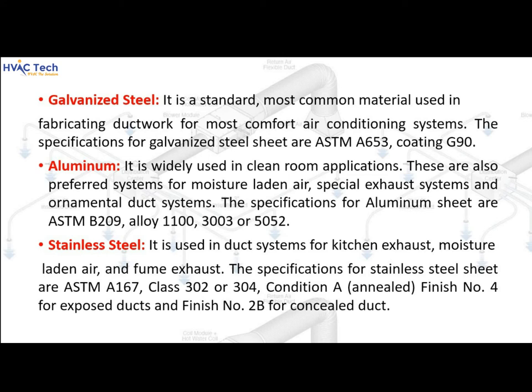Stainless steel is used in duct systems for kitchen exhaust, moisture-laden air, and fume exhaust. The specifications for stainless steel sheet are ASTM A167, class 302 or 304, condition A. Finish number 4 is used for exposed ducts, and finish number 2B for concealed ducts.